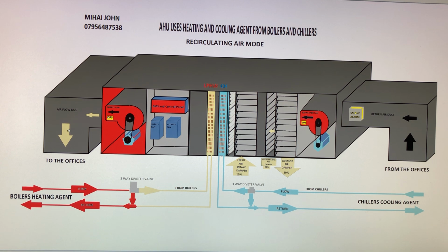It's quite simple. What I want you to remember instead are a couple of things. One, as you see this yellow spot, this is a differential pressure switch. Inside this supply air chamber, the pressure is negative, and inside the fan in a duct, the pressure is positive. This DPS will sense this and it will send an input to the BMS. That's how the BMS knows the fan runs. If the fan is not running, then you have to check.